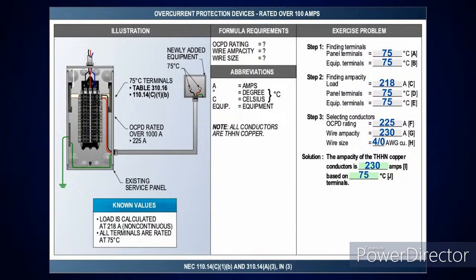The equipment and the panel are 75 degrees C. I've got a 218 amp non-continuous load. What's the next size overcurrent device above that, 218? Go over and look at Table 240.6(A) for your standard ampere ratings. That'd be a 225. Now I need to find a wire ampacity above that.